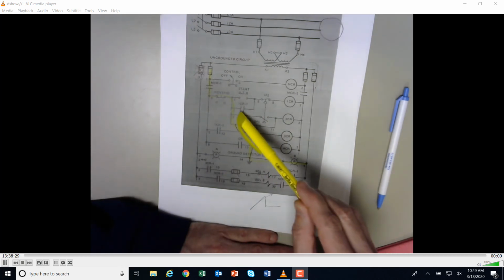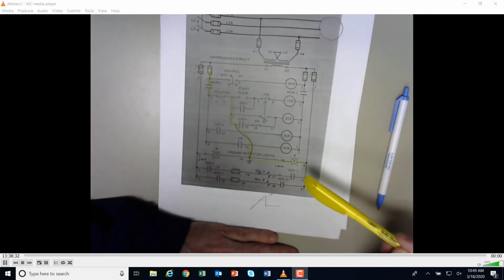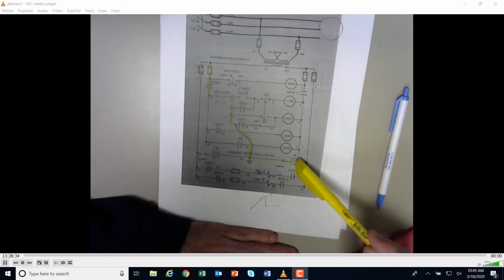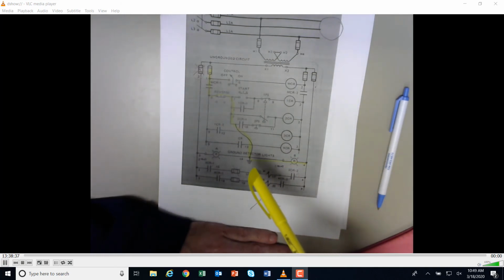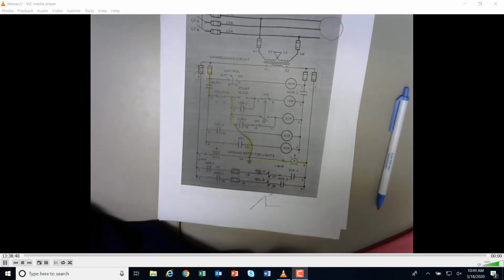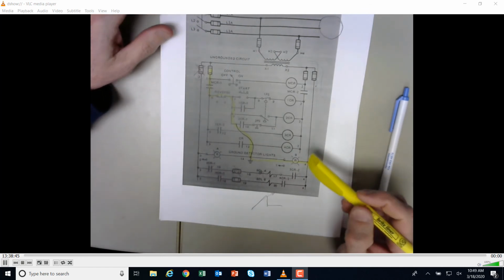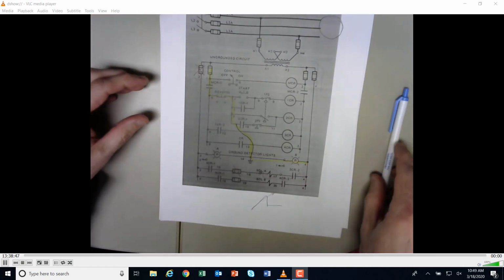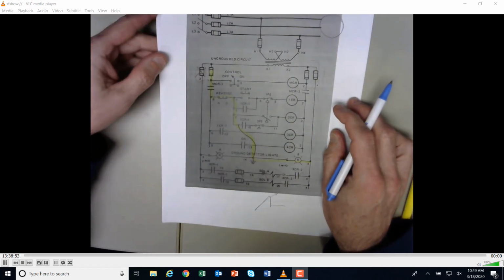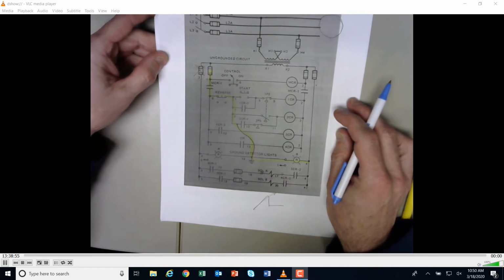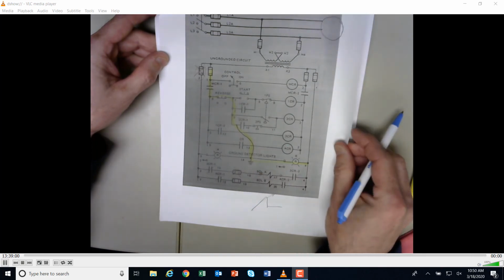And because I can go through and try all the circuits like that, when I finally get to the rung that causes this to come on bright, then I know that that's starting to put me in an area where my fault is. So that's the quick premise on the ground fault. And there's a difference between grounding and bonding and talking about earth and everything like that you'll get into in some later classes. But what you're going to do is try and look at the logic and see how this goes. So a couple other things real quick.